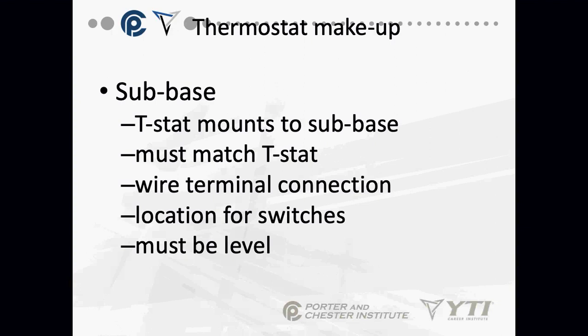The subbase is the component of the thermostat that holds the thermostat face on the wall, okay? It has all the wire terminal connections, and it has locations for switches. I'm less worried right now about the must-be level, okay, other than from an appearance standpoint. Does anybody still have a mercury thermostat in your house? Yes, I do. I have one. Okay, if you have a mercury thermostat or if you're dealing with a customer that has a mercury thermostat, that's where the must-be level applies, okay, because the mercury bulb has to be mounted level.